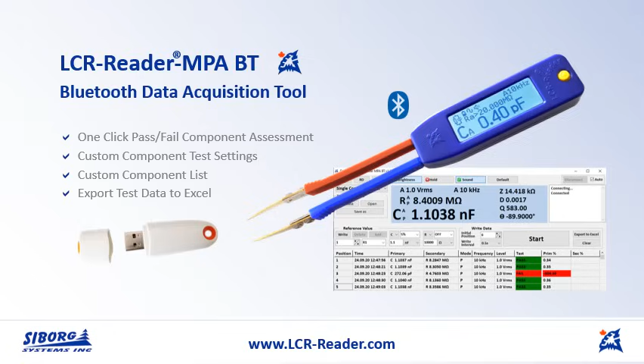It's called LCR-MPA Bluetooth Logger, and on the screen you see this main section of the screen with the parameters encircled in red. They are clickable, so when you click on those parameters you see the little menu that allows you to actually change the test parameters, and then it'll be used when you do the measurements on your device. The main feature is also being able to grant a pass or fail upon testing.